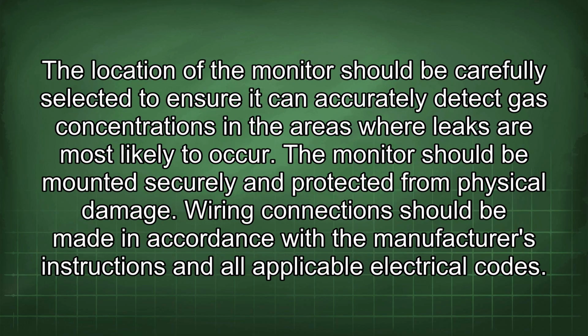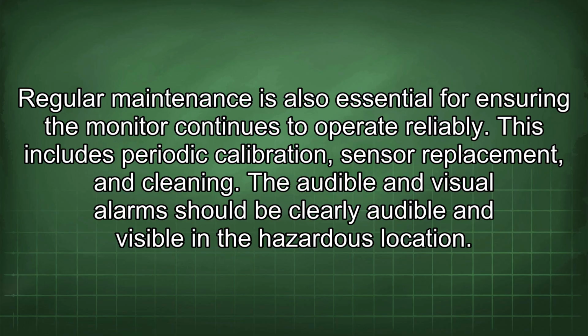The location of the monitor should be carefully selected to ensure it can accurately detect gas concentrations in areas where leaks are most likely to occur. The monitor should be mounted securely and protected from physical damage. Wiring connections should be made in accordance with the manufacturer's instructions and all applicable electrical codes. Regular maintenance is also essential for ensuring the monitor continues to operate reliably. This includes periodic calibration, sensor replacement, and cleaning.